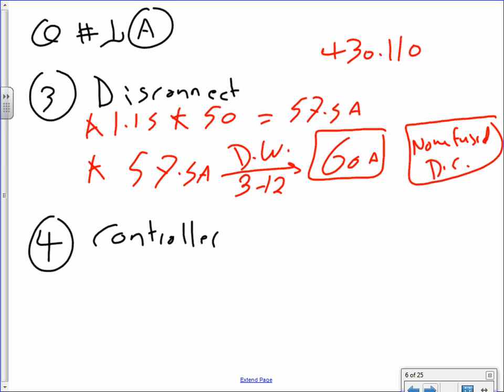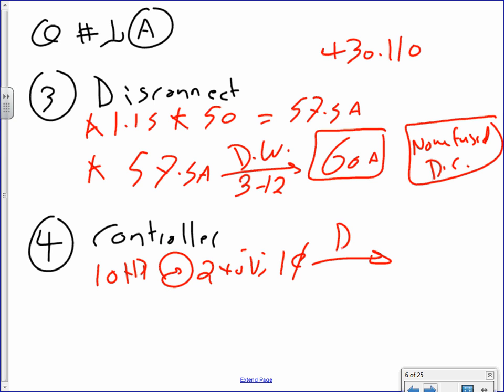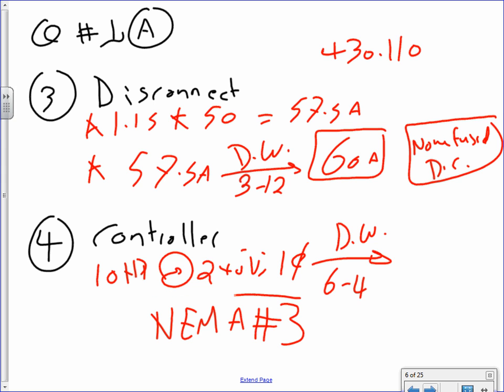The controller is so easy. You take the 10 horsepower at 240 volt, single phase, and take this one to the table. If you take it to table 6-4, that will get you a healthy NEMA size 3. So what you're doing is looking at the NEMA here. This magnetic starter is where they size them by NEMA 3. If you don't have the table on the test, you just write 10 horsepower, 240 single phase. Did you hear me? That's it.